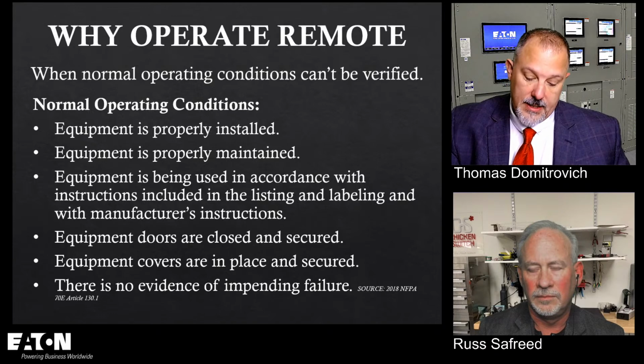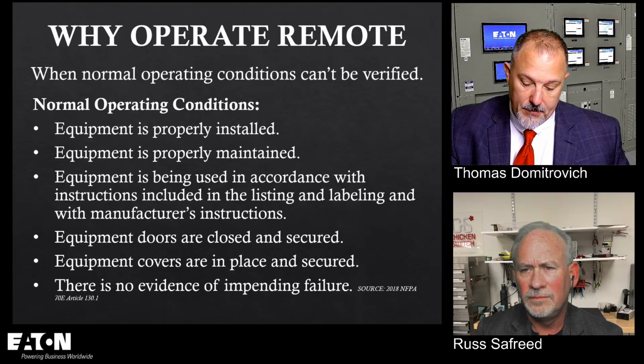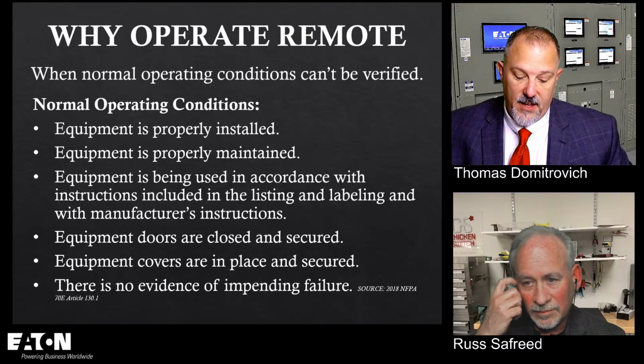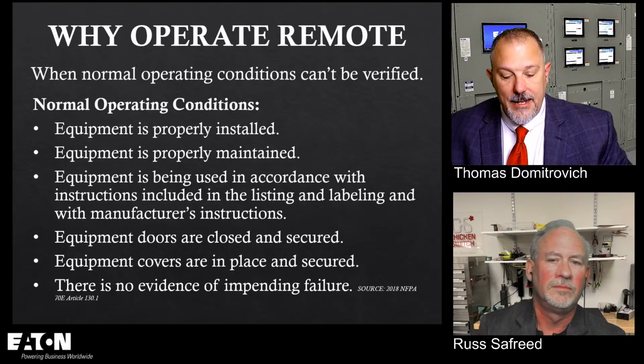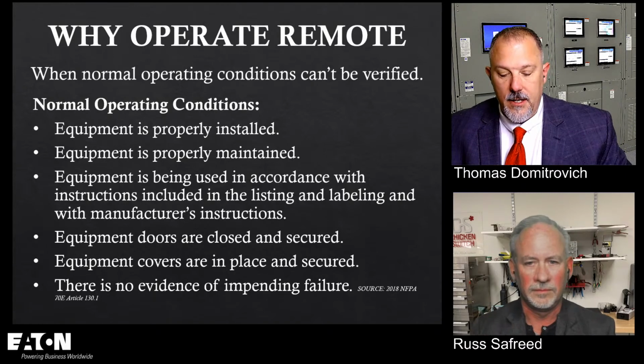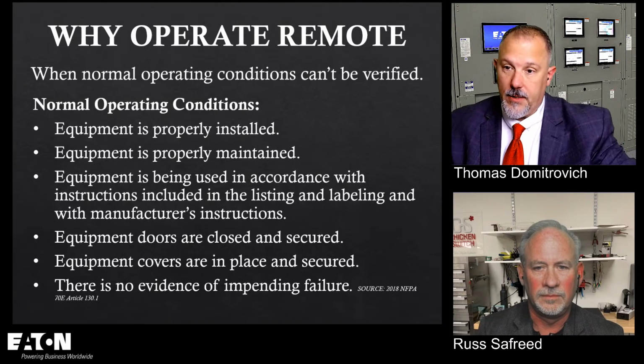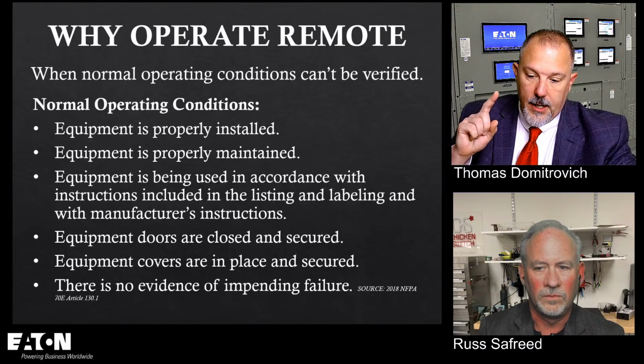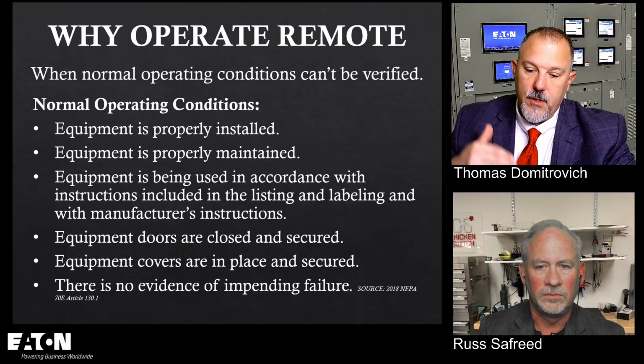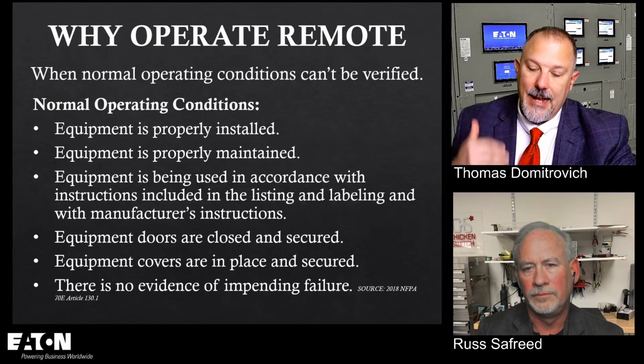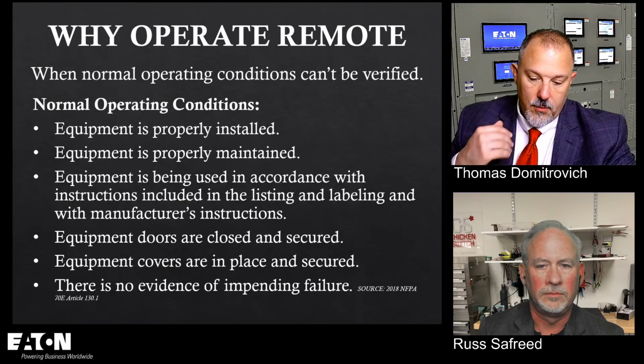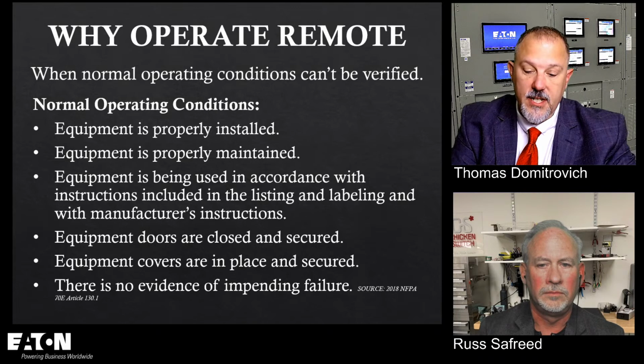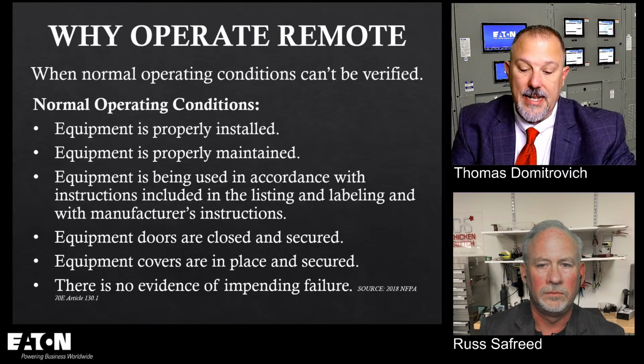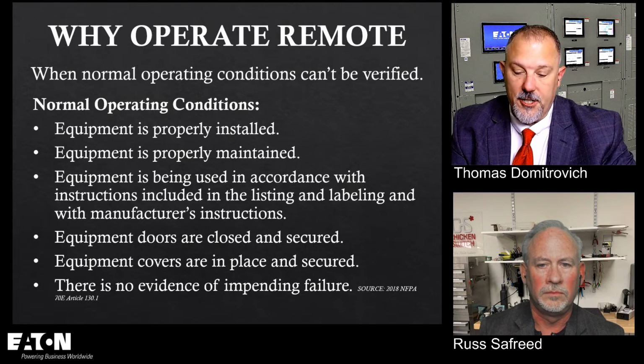Robert of Omaha brings up a good point. There is a table, 130.5, estimate of the likelihood of occurrence of an arc flash incident for AC and DC systems. There's a task, there's equipment condition, and then there's likelihood of occurrence. If you look at operation of a circuit breaker or switch the first time after installation or completion of maintenance in the equipment, any condition, and yes, there's a likelihood of occurrence.